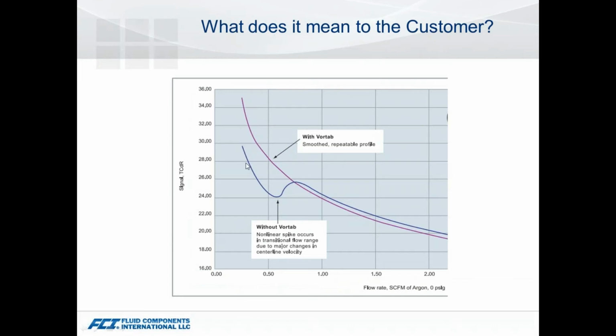If you look at the blue line, going through that Reynolds number transitional zone you get that fishhook, that nonlinearity, and it can be as much as 10%. So when we run your application and recognize we're in that transitional zone, one option is to go with that Vortab integral to the flow element, and that gives you a smoothed out, fully linear output. The Vortab itself doesn't create a laminar or turbulent condition; it's very repeatable across the entire flow range, and that's how the meter's calibrated.